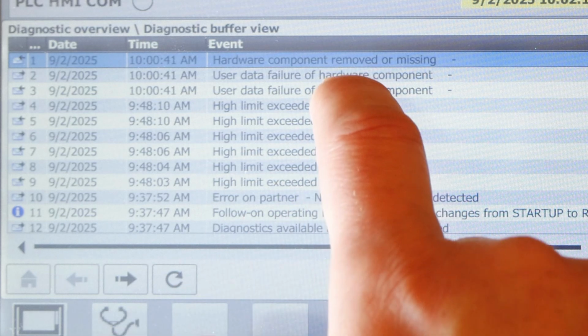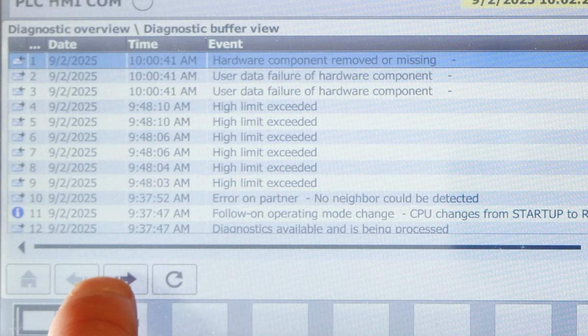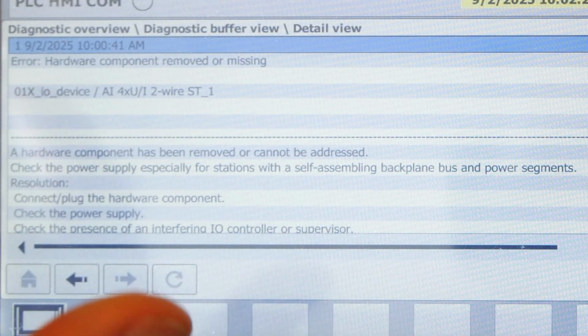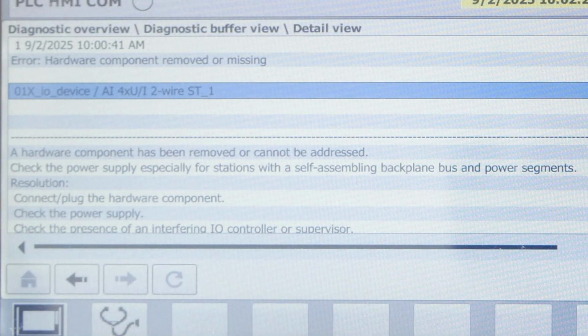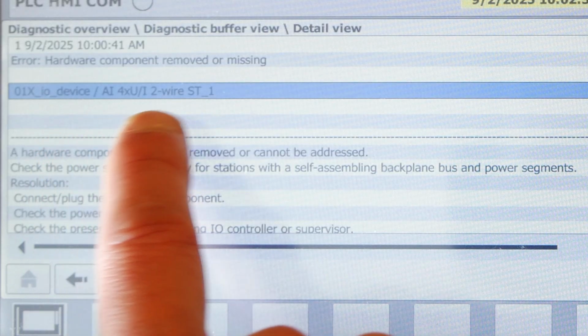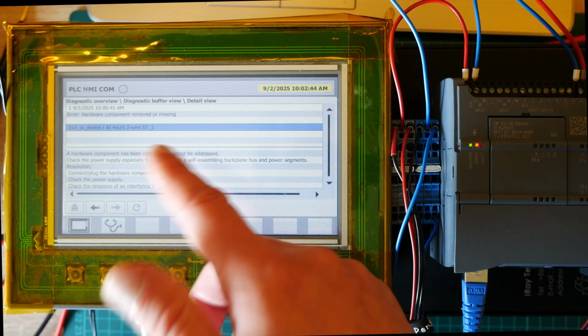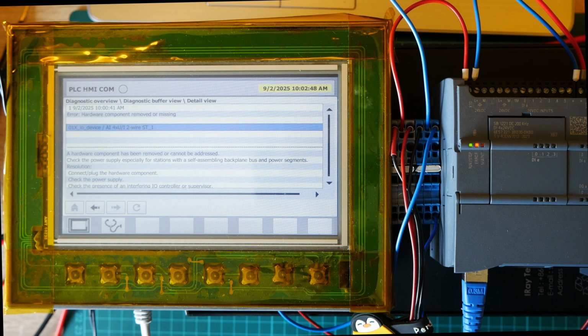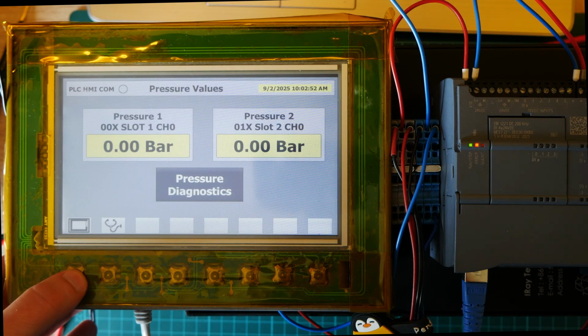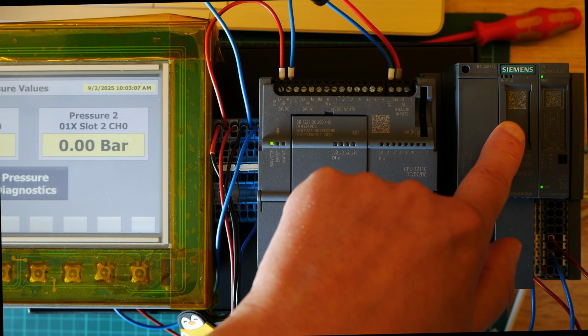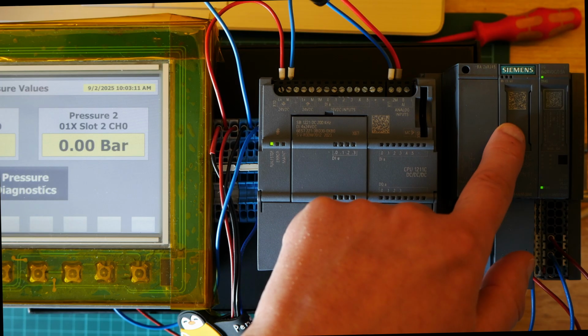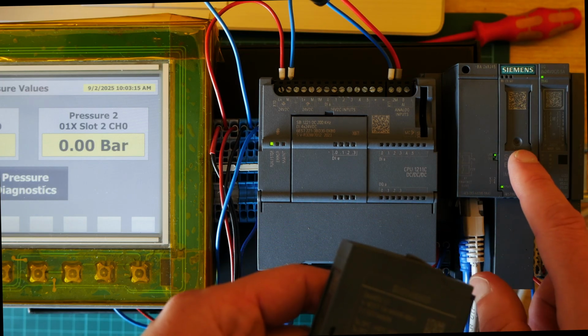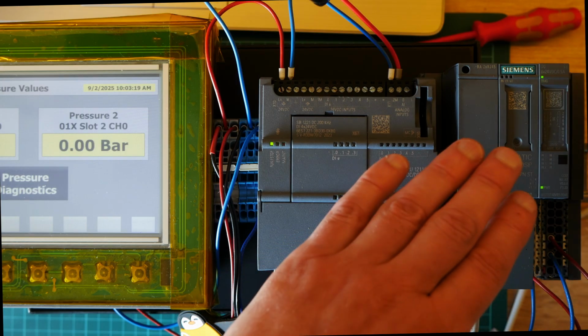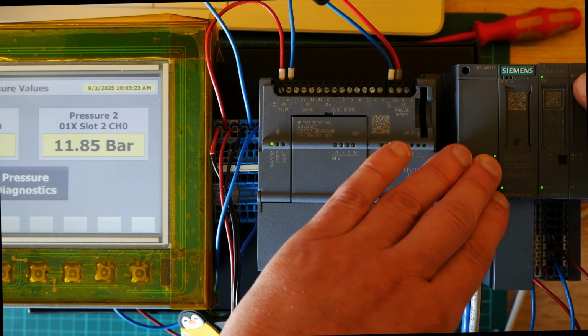And if we press to select this event, to see what's going on, and press this arrow to check it out, what we have here is information: 01X input output device, analog input four channel card is missing. And in fact, yes, it is missing. I just removed it. So it gives us a very good indication of what is actually happening, and where to go and how to fix it. If you have firmware version 1.1, you cannot remove modules while this is working. But if you upgrade the firmware, it's hot swappable, so it's not an issue. Yes?